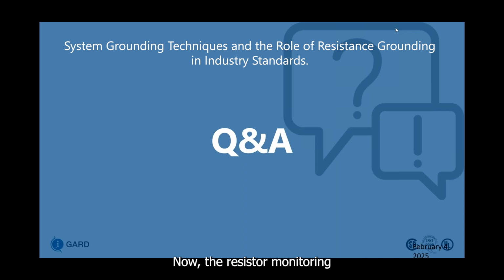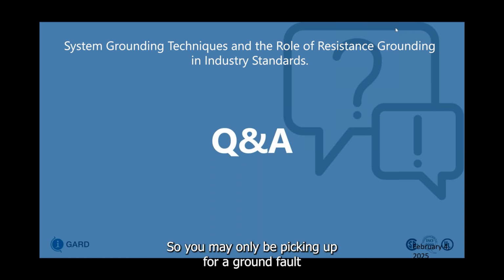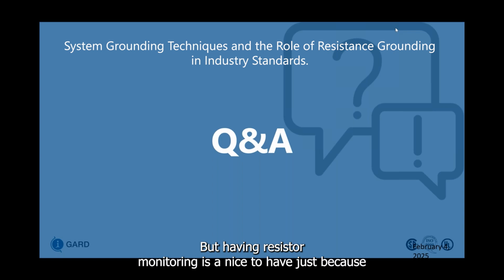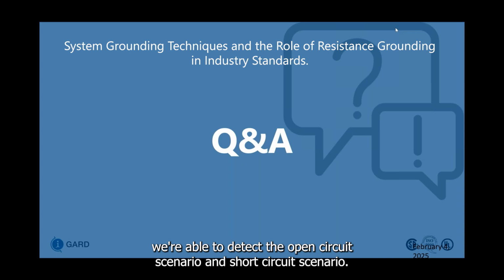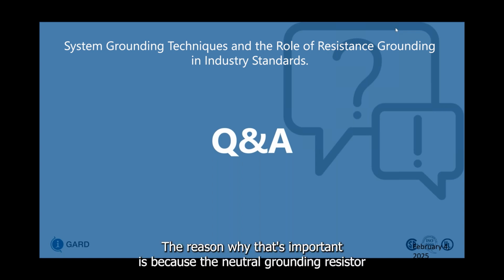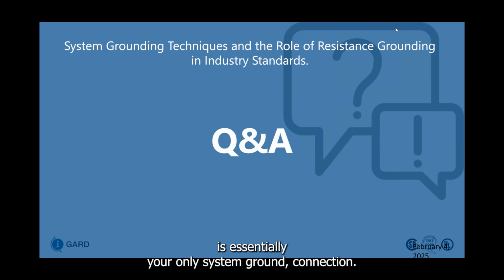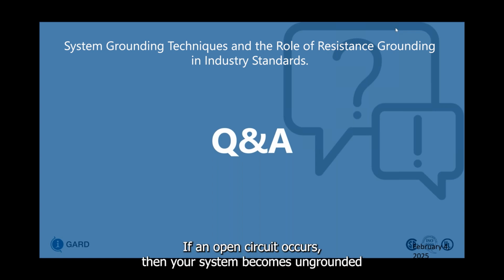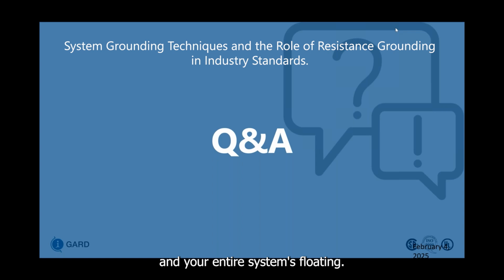Now, the resistor monitoring is a new code requirement, especially for us in Canada. In the US, this code requirement does not exist yet, so you may only be picking up for ground fault. But having resistor monitoring is a nice to have just because we're able to detect the open circuit scenario and short circuit scenario. The reason why that's important is because the neutral grounding resistor is essentially your only system ground connection. If an open circuit occurs, then your system becomes ungrounded and your entire system's floating.